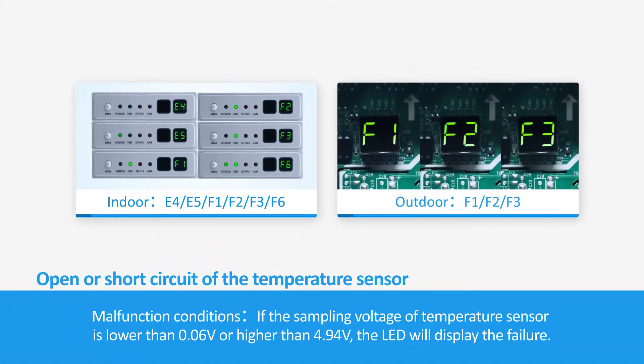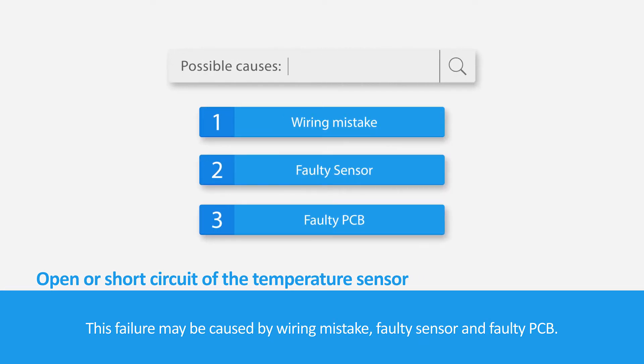Open or short circuits of the temperature sensor are malfunction conditions. If the sampling voltage of the temperature sensor is lower than 0.06 volts or higher than 4.94 volts, the LED will display a failure. The failure may be caused by a wiring mistake, a faulty sensor, or a faulty PCB.